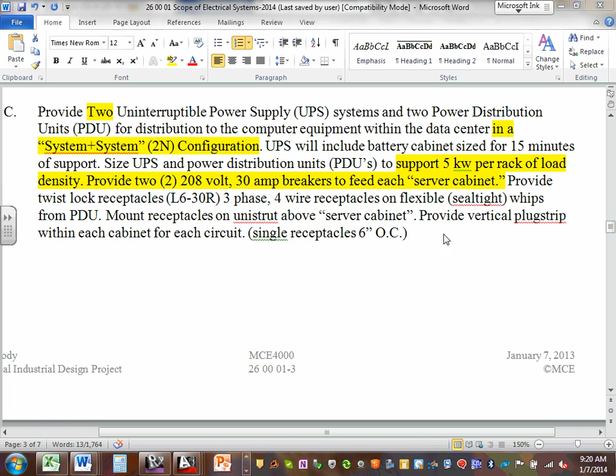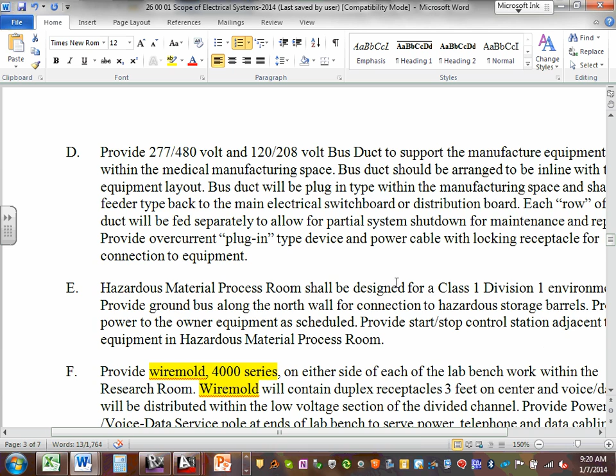That's pretty close to our data center area. There's going to be handfuls of different locations where we're going to be doing bus duct, feeding bus duct with manufacturer equipment. It's going to be plug-in type bus duct. You can get all sorts of different types of bus duct, but plug-in seems to work the best. There's a hazardous material room that's Class 1, Division 1. We're going to need to focus on the section of the code that's talking about explosion-proof fixtures and sealed light switches and sealed light fixtures and things like that. There's a handful of things we have to do to keep that room safe.